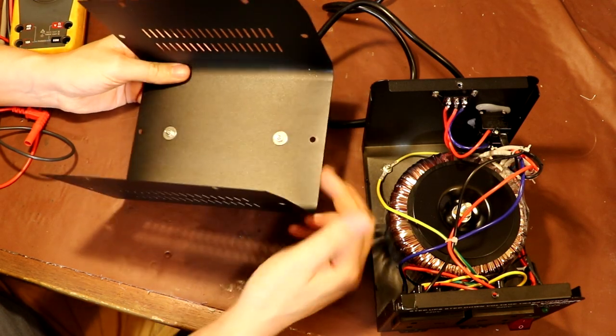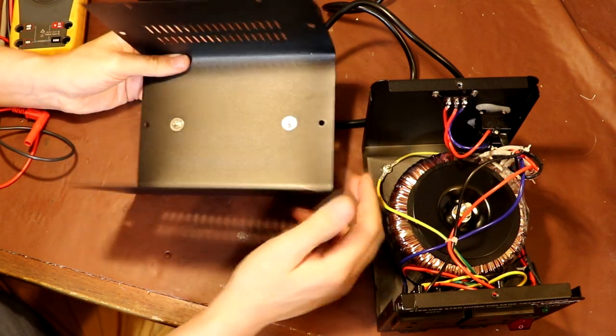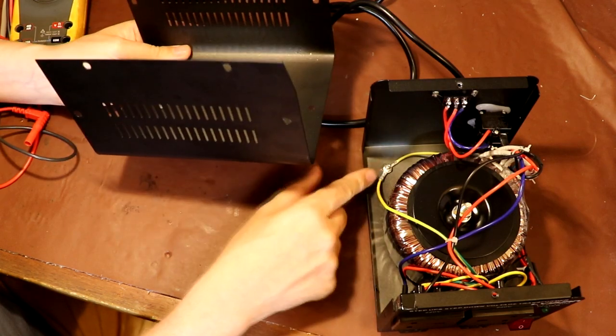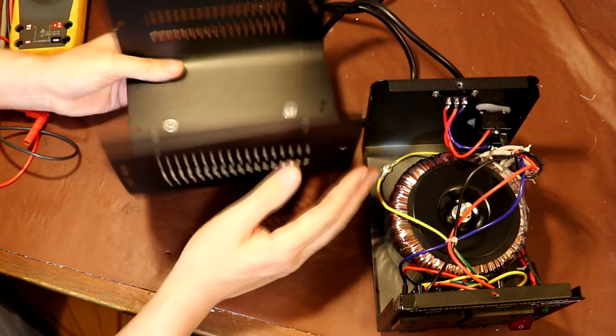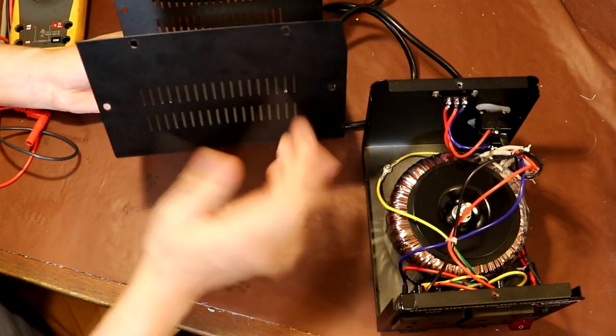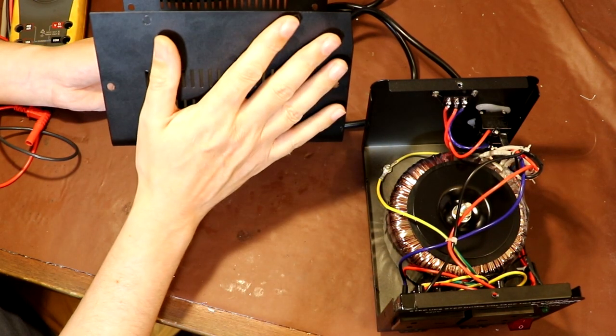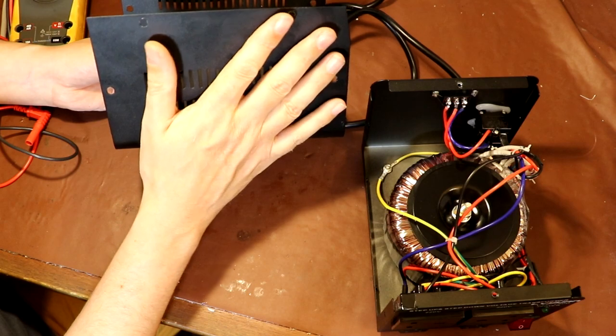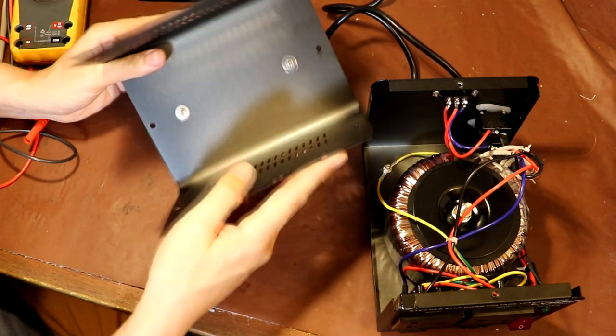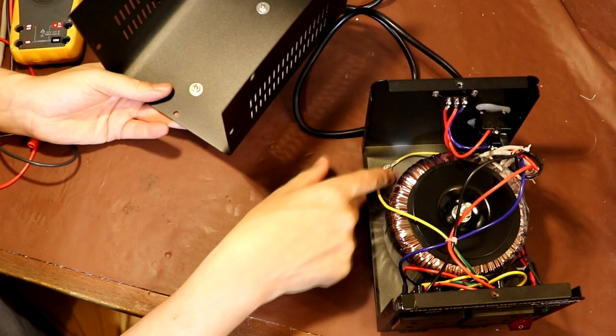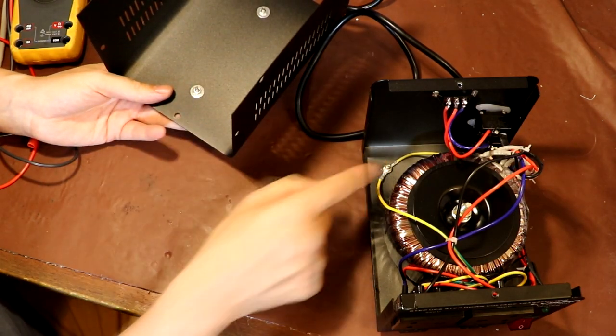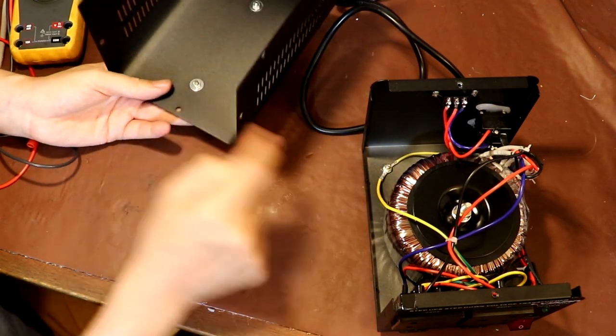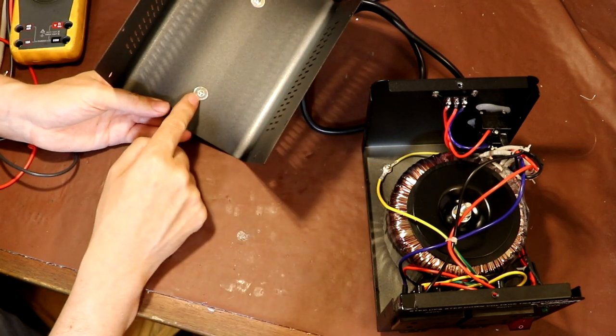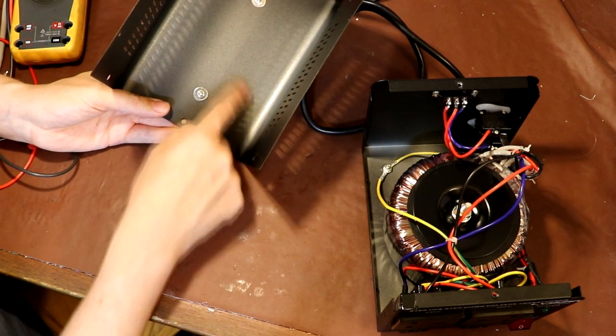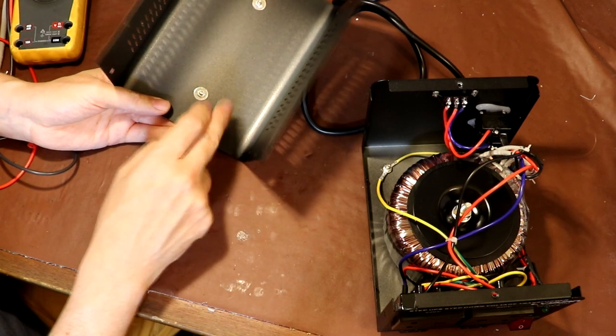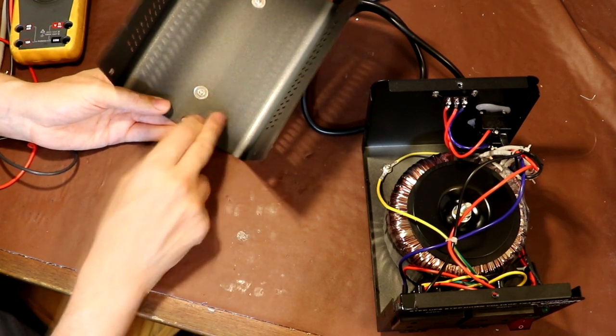So really what you would want to see is an earth wire between this top cover here and here, so that it always remains connected, because what could happen is a wire could come off here, it could touch the side of the unit, you put your hand on it and you receive a really nasty or fatal electric shock. So this cover must be earthed. So what I think we'll do with that is we'll just disconnect here, and I'm going to put a short link wire between this earth stud and the top cover. We'll scratch the paint off over here, and then we can actually guarantee that this top cover is going to be earthed. It is belt and braces, but it's the best way to do it.